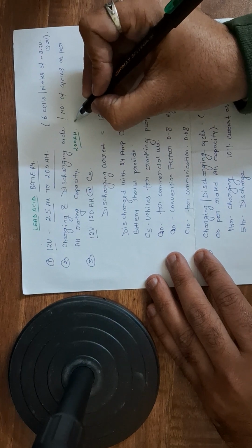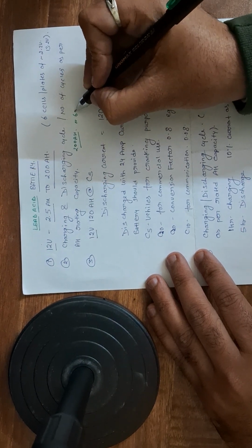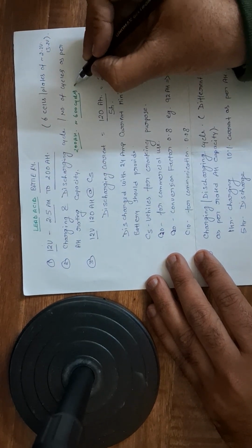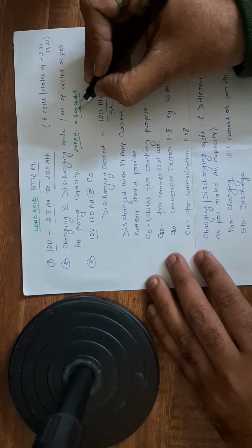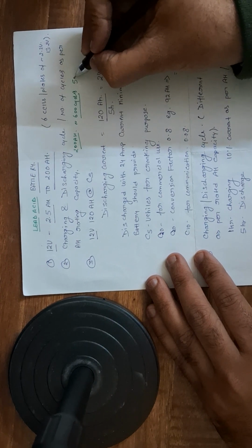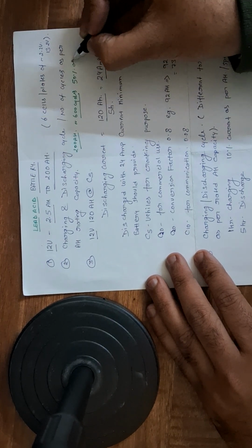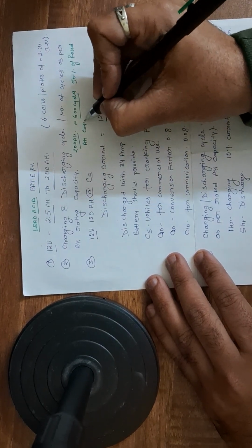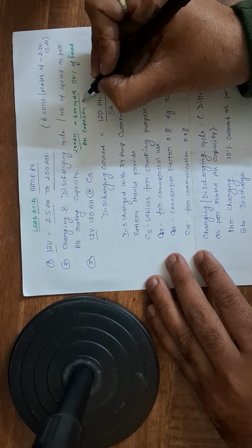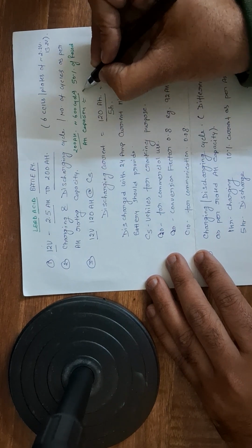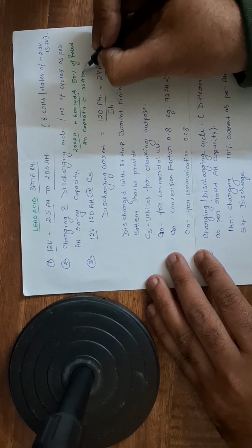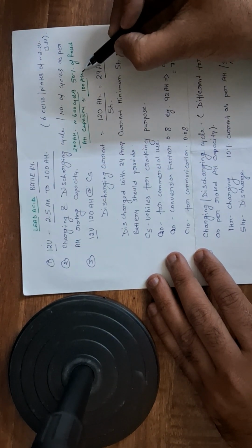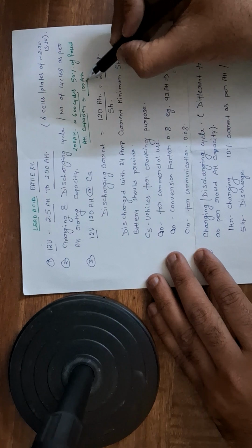Till its last cycle, approximately 600 cycles, till its last age, it should give 50% of its rated AH capacity. That means 100 AH minimum. At the last cycle, the battery should give at minimum 100 AH capacity.